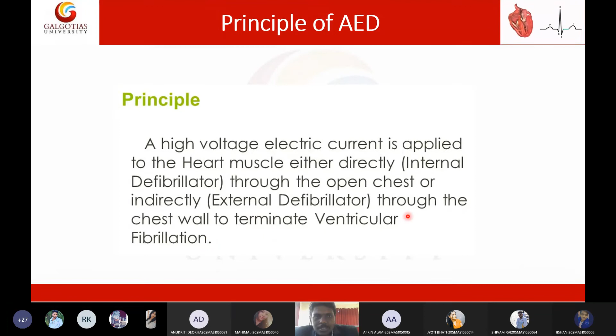So this is an actual picture of AED. This is the AED box, and we need to attach a connector to the AED, and it will have positive and negative electrodes. One electrode will be kept on the left shoulder, this electrode will be kept on the right shoulder, and this electrode will be kept on the left side abdomen. After that we need to turn on the device. It will read the patient's electrical activity, and it will tell us, yes, I'm going to give a shock, please don't touch the patient.